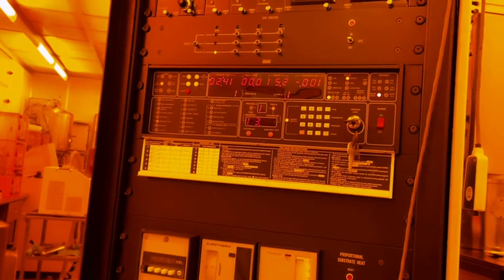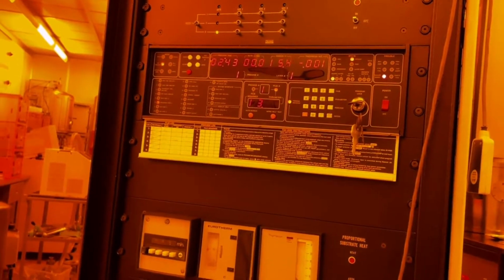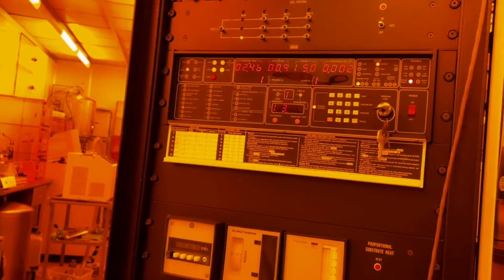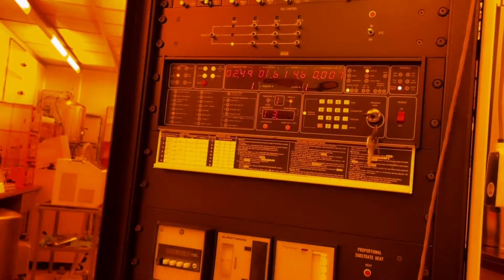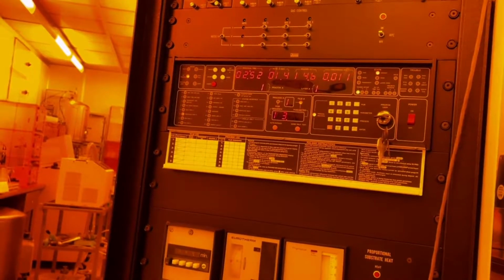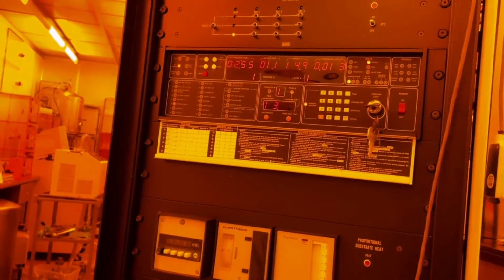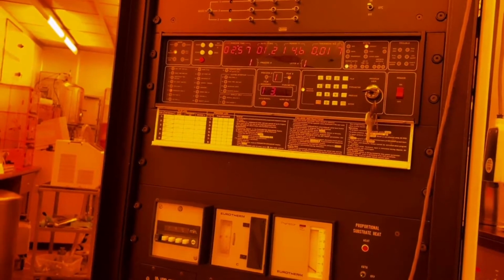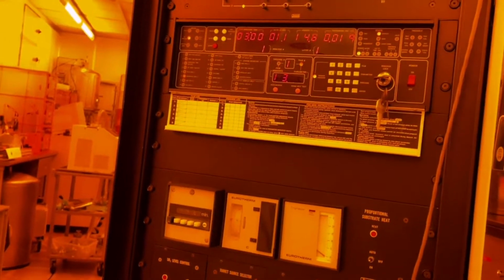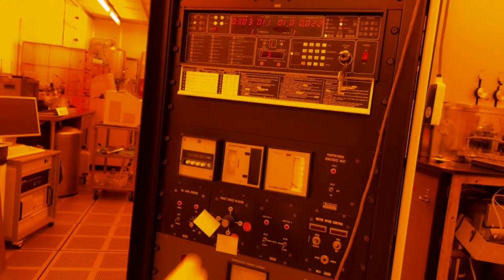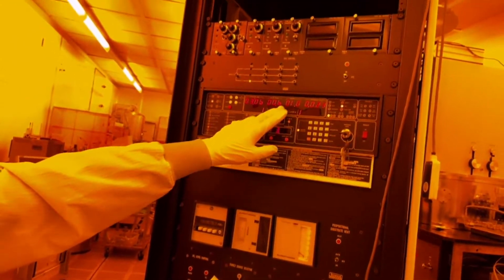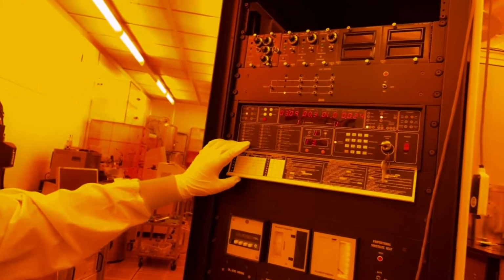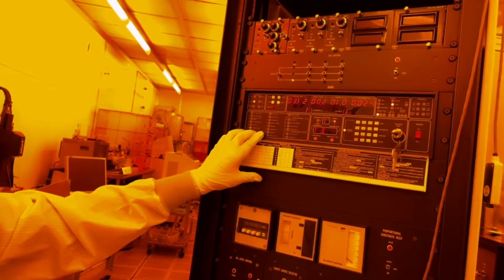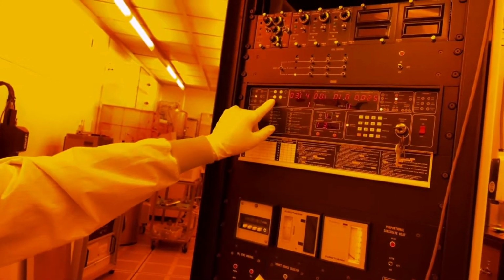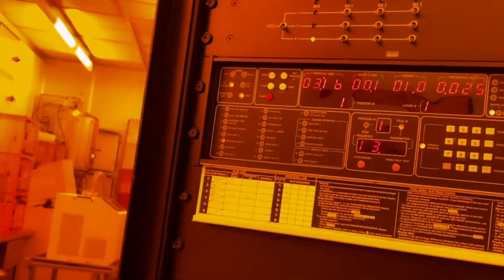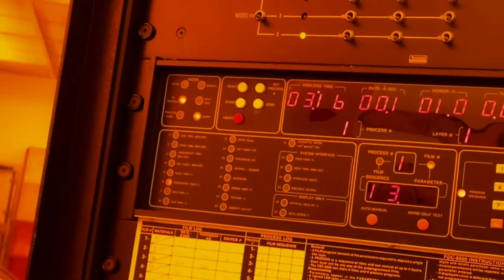The power is going to raise until we reach the proper rate that we need to coat our sample at 1 angstrom per second. So see, now it's gotten to that point. It's now doing a feedback loop. And as soon as this hits 2 nanometers, or 0.02 kiloangstroms, it's going to shut the shutter again. And again, now you can see the shutter is closed and our power has stopped. At this point, this sequence will try and go into the next step, which is a silver deposition. But since we don't need that, we're just going to press the abort button now. And it's going to be steady in this state.